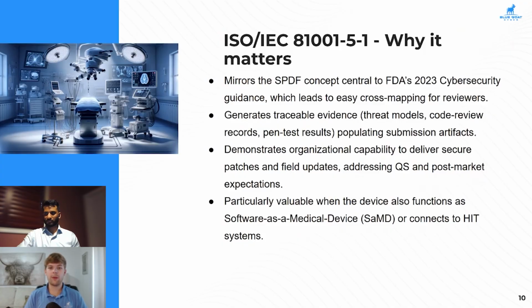Now, we're looking at easily traceable evidence, which is going to be great for populating these submission artifacts. This will be things such as threat models, code review records for that static and dynamic testing, penetration testing results, and how we're tracing them all back to each other. All of these are separately required by the FDA, as well as the traceability between them. This also shows the organizational capacity to deliver secure patches and field updates, addressing quality system and post-market expectations. This is something the FDA has really been trying to emphasize recently: having a process to deliver patches to fielded devices.